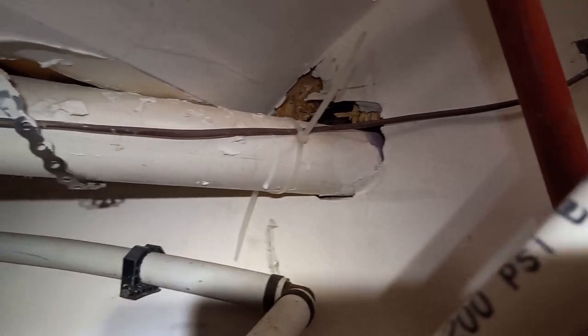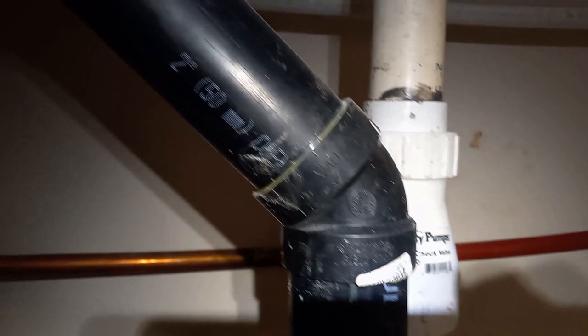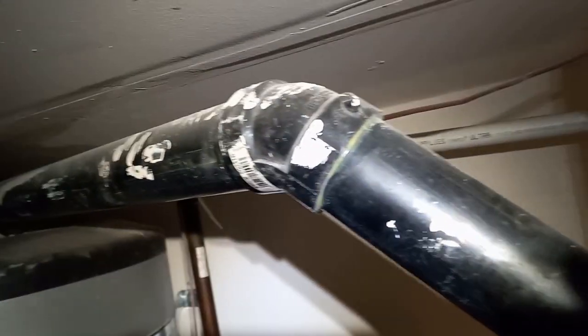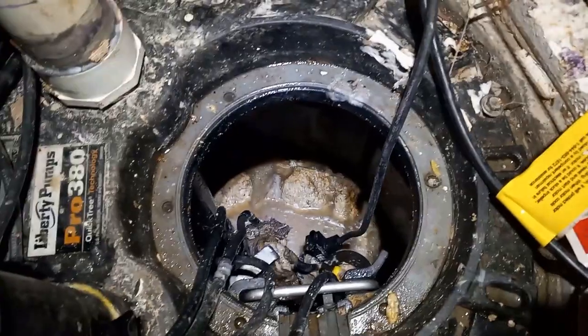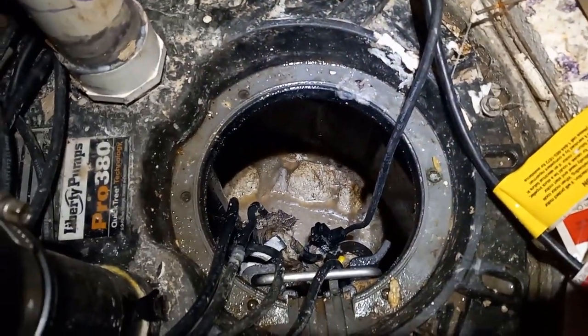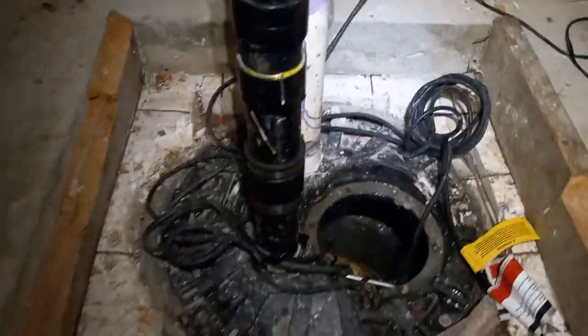The pipe turns and keeps going to the sanitary sewer line, which is slightly higher than the basement, then it goes by gravity into the city. The second pipe here is just the vent — it's an empty pipe, minimum two inches for a sump like this. It goes through the roof or connects to a different vent. It prevents the buildup of gases inside the tank, and those gases are flammable — if there's a spark that could cause a small explosion. So the vent for the sump is extremely important.